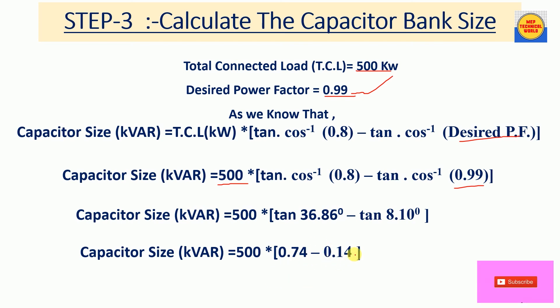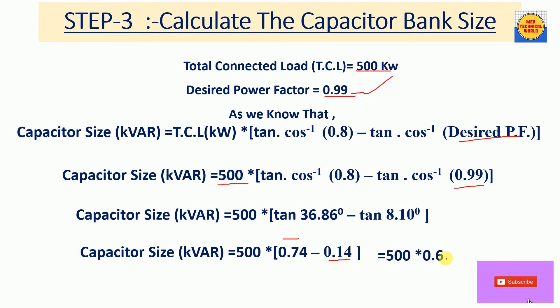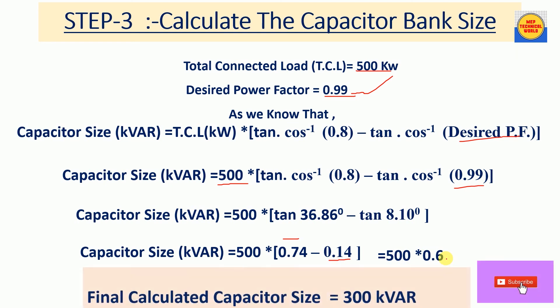Tan(36.86°) equals 0.74 and tan(8.10°) equals 0.14. Subtracting 0.14 from 0.74 gives 0.60. So the calculation becomes 500 × 0.60, and our final calculated capacitor bank size is 300 kVAR.